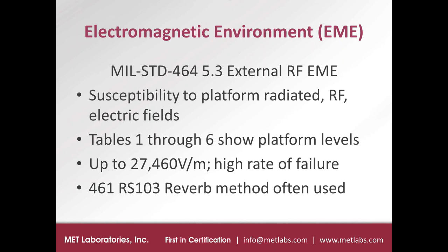And some of these levels include radiated fields up to 27,460 volts per meter. And there's a high rate of failure that's experienced in the lab when we test for these types of high levels. One thing to note is that that extreme level is a pulsed field, so it doesn't have a long duty cycle. There's not a lot of continuous energy there at all, but the voltage during that quick pulse is very high. And 461 RS-103 using the reverb method is what's often used to perform this type of testing for this requirement. I've also heard that sometimes testing is done on military bases with the actual radar equipment.